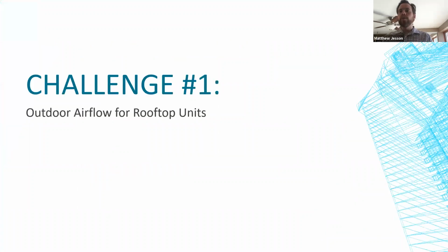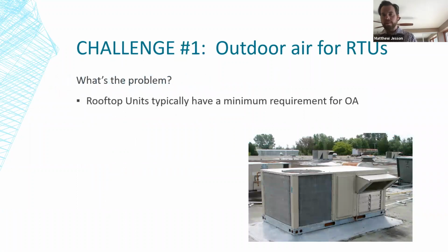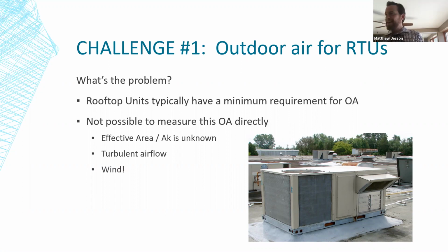So to get into the actual specific challenges I want to talk about, the first one is one that I wanted to make sure that we covered because it comes up very frequently. Pretty much any job that has rooftop units, this will come up. And it's outdoor air for rooftop units. Rooftop units will usually have a minimum requirement for outdoor air because of code, but it is really not possible to measure that outdoor airflow directly.